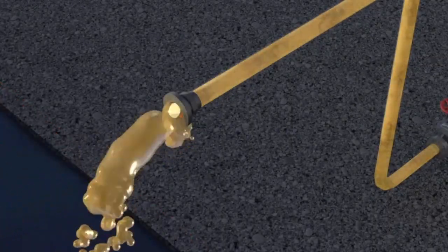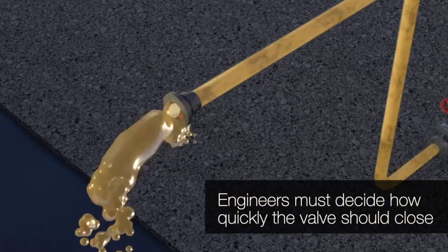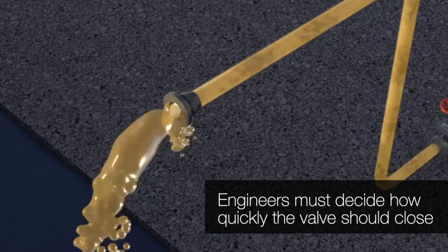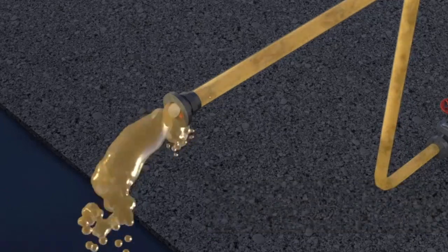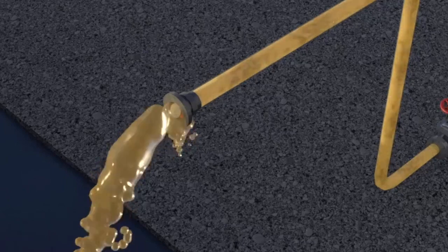Should a ship break away from the dock, engineers must decide how quickly the valve should close. A 30-second, slow-closing valve may decrease the initial surge in pressure, however thousands of gallons of fuel would be discharged to the environment.